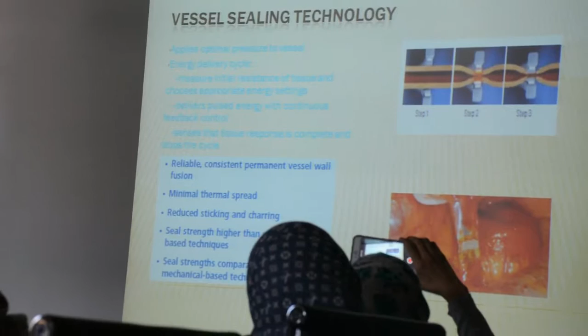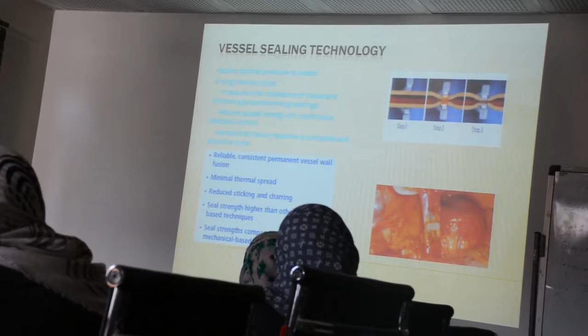Applies optimal pressure to the vessel. Energy delivery cycle: measure initial resistance of the tissue and choose the appropriate energy setting. Deliver pulsed energy with continuous feedback control. Senses that the tissue response is complete and stops the cycle. In this picture, very reliable, consistent, permanent vessel wall fusion, minimal thermal spread, reduced sticking and charring, seal strength higher than other energy-based techniques, seal strength comparable to existing mechanical-based techniques.